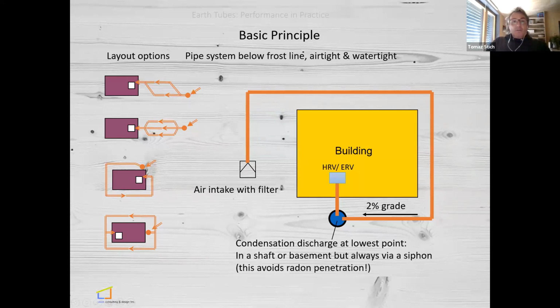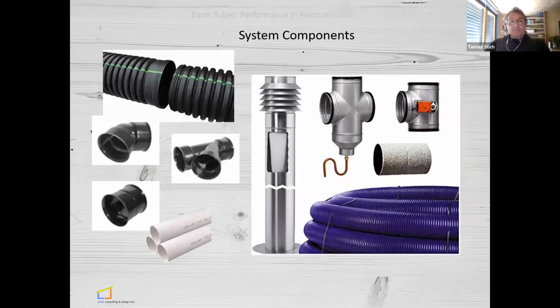Okay, system components. You see some plastic piping here on the left. Typically, this is what's buried underground. This one here is an HDPE pipe, high density polyethylene, with elbows, Ys, couplers, or you can use a PVC pipe as well. Those here on the right-hand side are metal piping, where you have a condensation drain here at the lowest point. You have a shutter here, and this is your air intake on the outside.